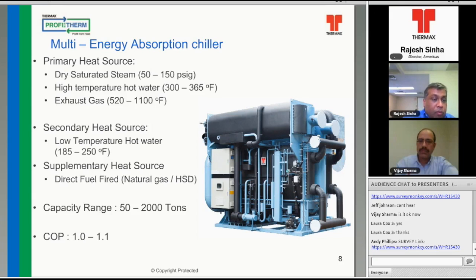And there is typically a secondary heat source, which is low temperature hot water, typically at 185 to 250 degrees Fahrenheit. Now, this could be deployed in conjunction with a reciprocating engine, which would have exhaust gases. The exhaust gases would work as a primary heat source, and the jacket heat, which is typically rejected to the radiator, would act as a secondary heat source. This is one of the newest products, which has been around for 5 to 6 years, where we already have close to 30 to 40 installations of this type. Not to mention the overall absorber installation base here in the U.S., which currently would be close to about 400.